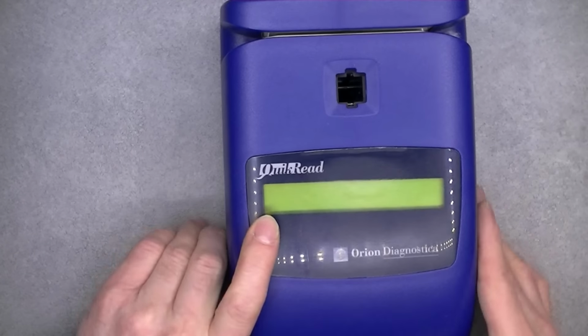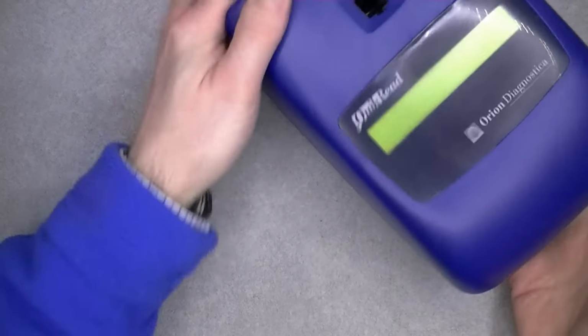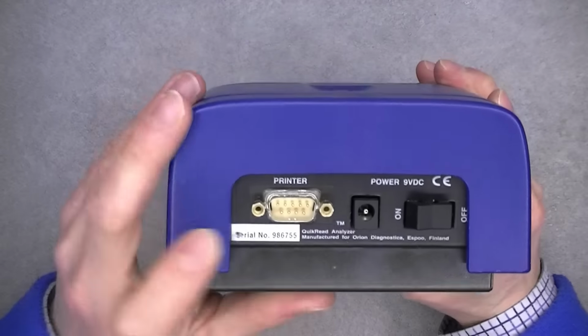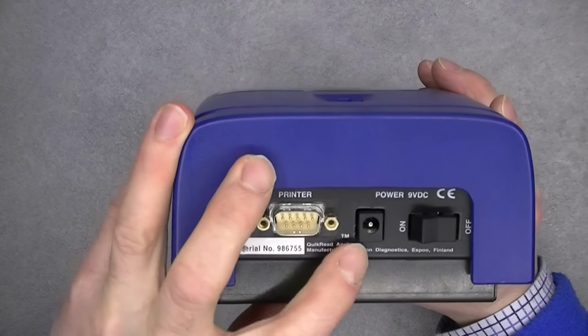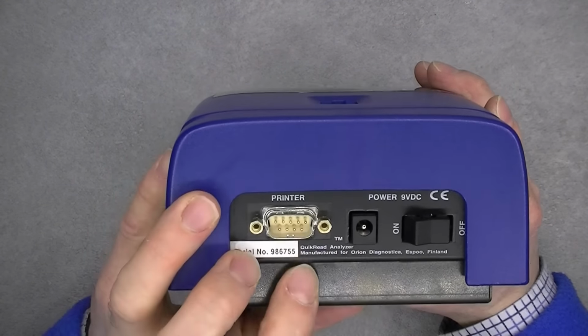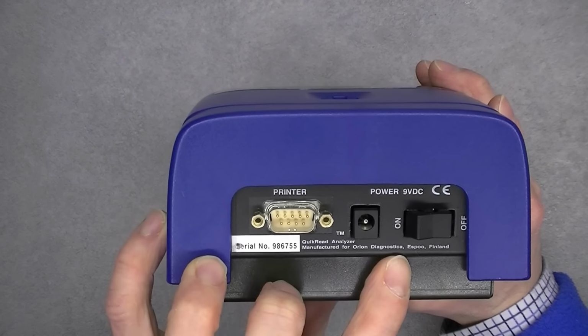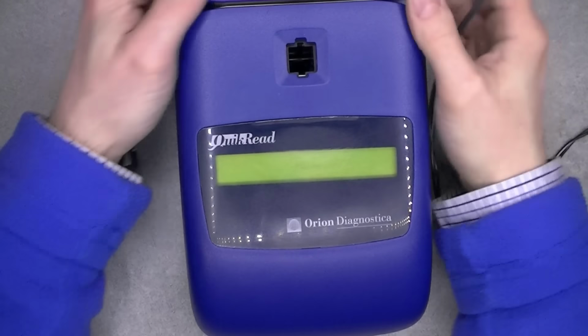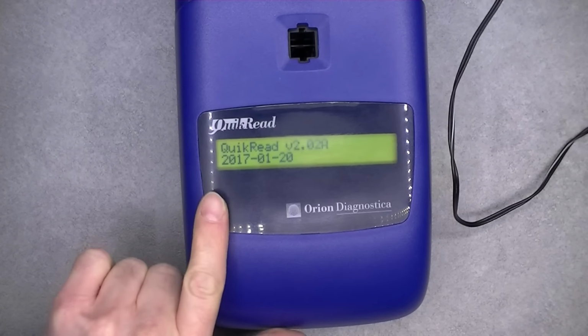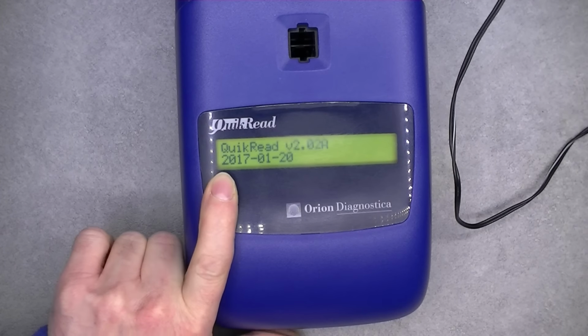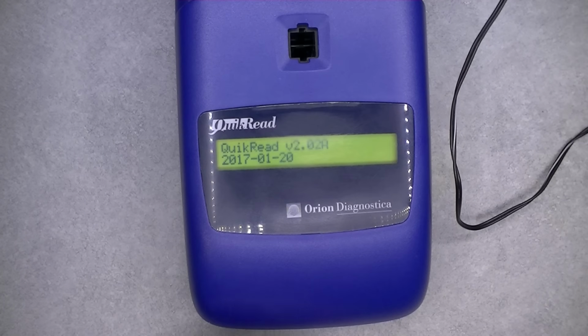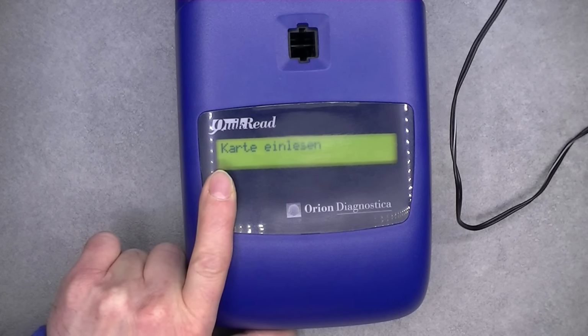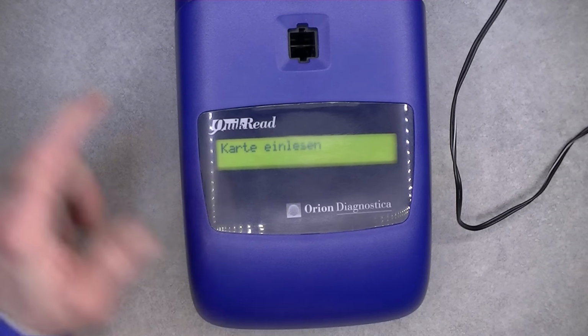So we just have a 2-line LCD display, no user interface at all, except for these 2 inputs. On the back we have just what seems to be some kind of a serial port, DC adapter and on-off, and it is made for Orion Diagnostica in Espoo, Finland. So if you power it, what happens? In fact, not much. It will just beep. So it is interesting to note there is the time and date in memory, and it is accurate, by the way, and it is telling you in German to insert the card.